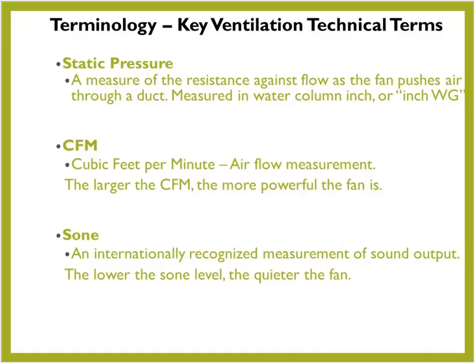Static pressure is measured in inches of water gauge. So when you look at a piece of equipment in a catalog or online, that's how you'll see the CFM performance referenced. You'll see it performance at 0.2 inches of water column or 0.25 inches of water column. Panasonic has all of their product tested at 0.25 because we feel that's a more realistic install. HVI normally does the testing at 0.1 inches of water gauge, and we actually feel that that's not a real-world install application, especially since a lot of product is installed with flex duct. We feel that 0.25 is a better test of real-world performance, so we have all of ours tested and published that information. So the big thing here is to reduce the amount of static pressure to help the fan perform at its optimum level.